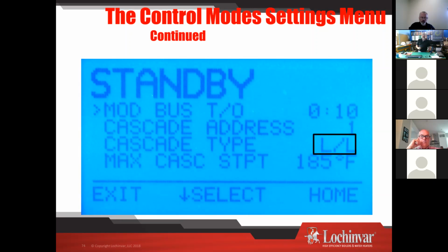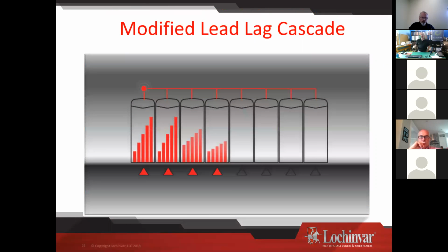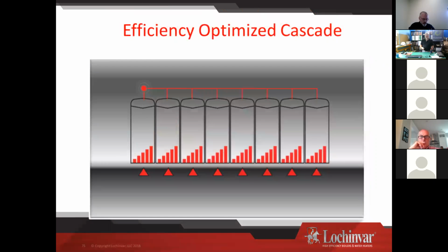Most often in a residential application, we use that lead lag where we're going to run one boiler as hard as we can until we can't keep up. Then we bring that next boiler on. But we'll generally run one boiler to like 90% before we fire off a second boiler. In efficiency optimized, we have them run together. So there's your modified lead lag. This would be your efficiency optimized.